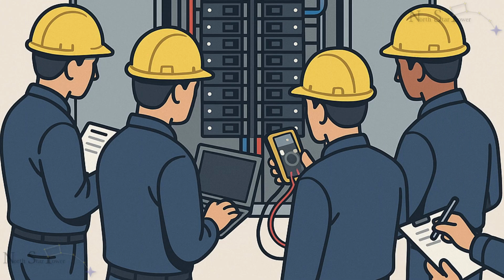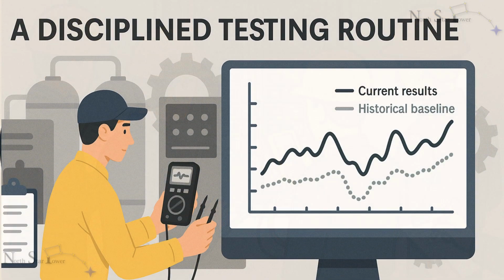Understanding the standards is essential, but conducting testing is what provides true protection. Much like a medical exam, no single procedure can fully evaluate a component's condition. Instead, a combination of assessments is required to gain a comprehensive understanding. A disciplined testing routine not only verifies that equipment functions within specifications, but also enables predictive maintenance based on long-term data trends. Comparing current results with historical baselines helps identify early signs of degradation and schedule interventions before a failure occurs.